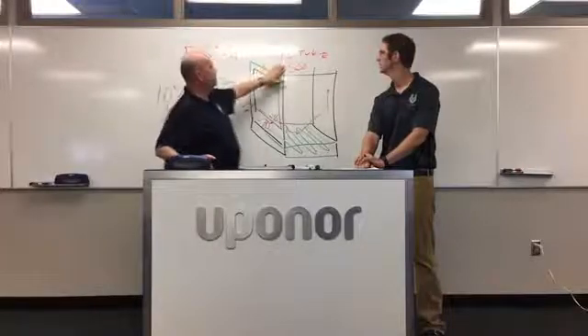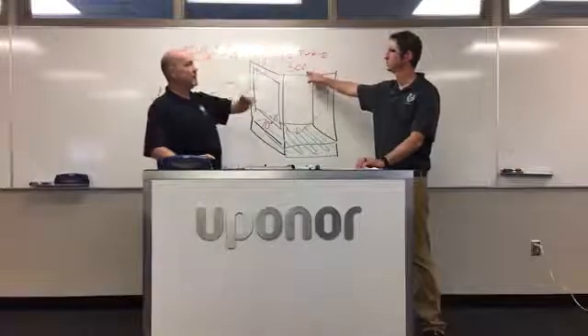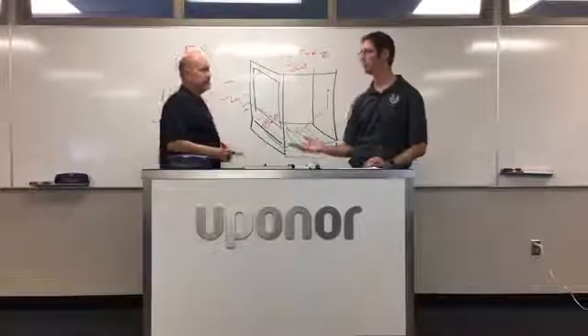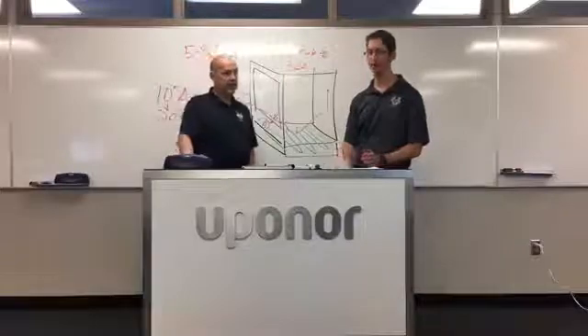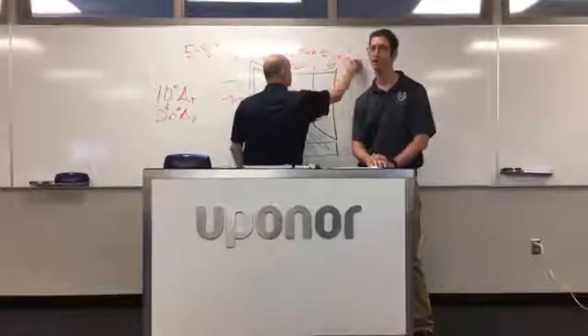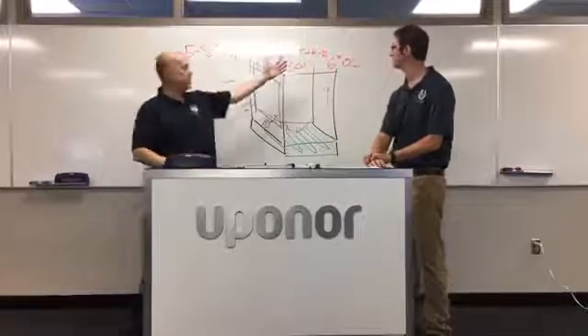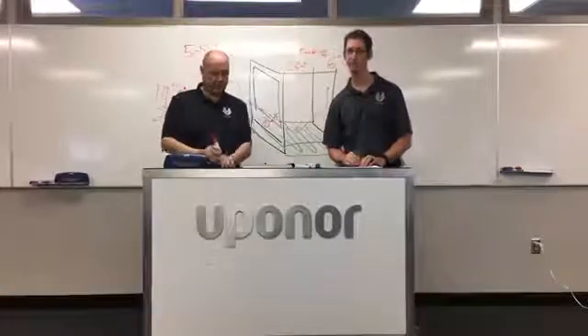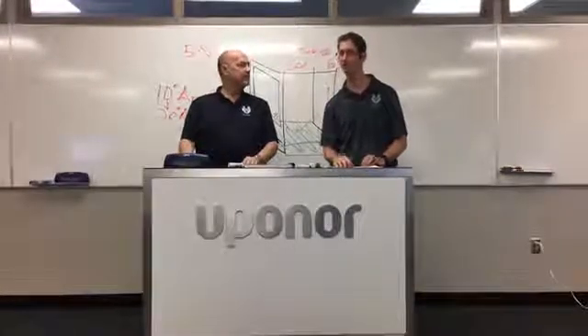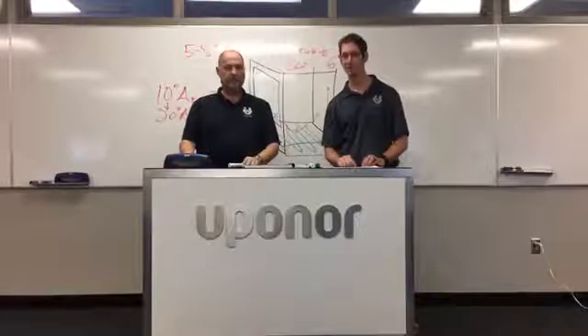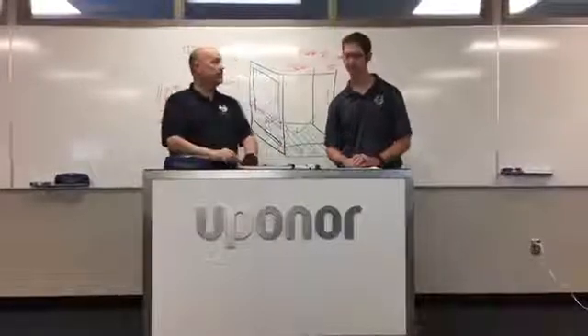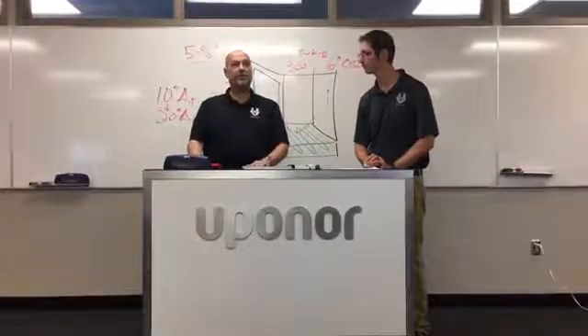Those 300-foot loops with five-eighths inch tubing won't cover the same area that half-inch tubing would in a heating system, mainly because you need narrower tubing spacing for cooling — about six inches on center rather than twelve. If you're watching and you've never done a cooling system, the costs are adding up in your head, but a cooling system design will pay for itself over the lifetime of the building.